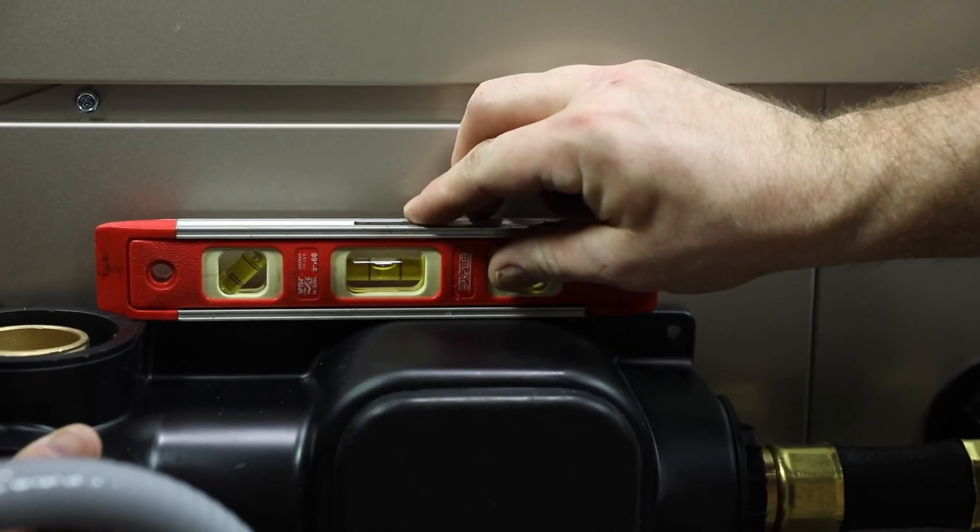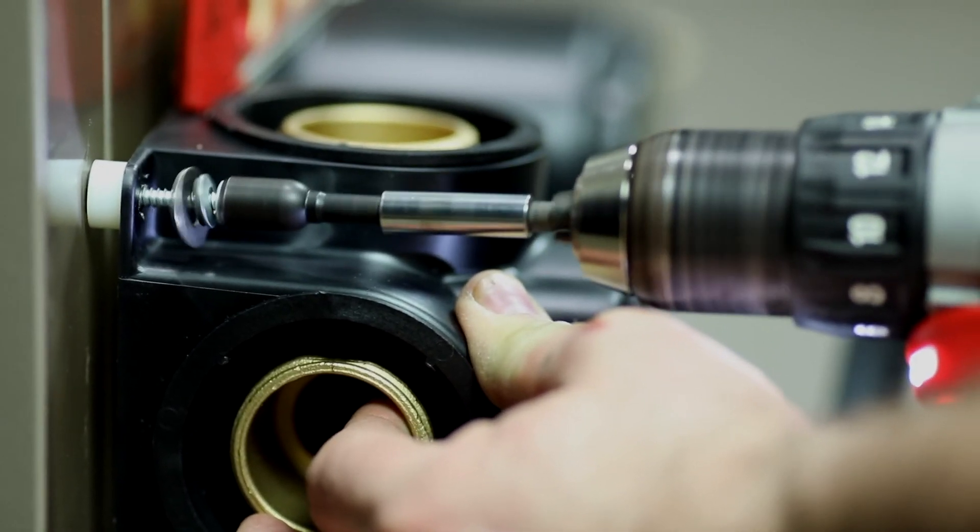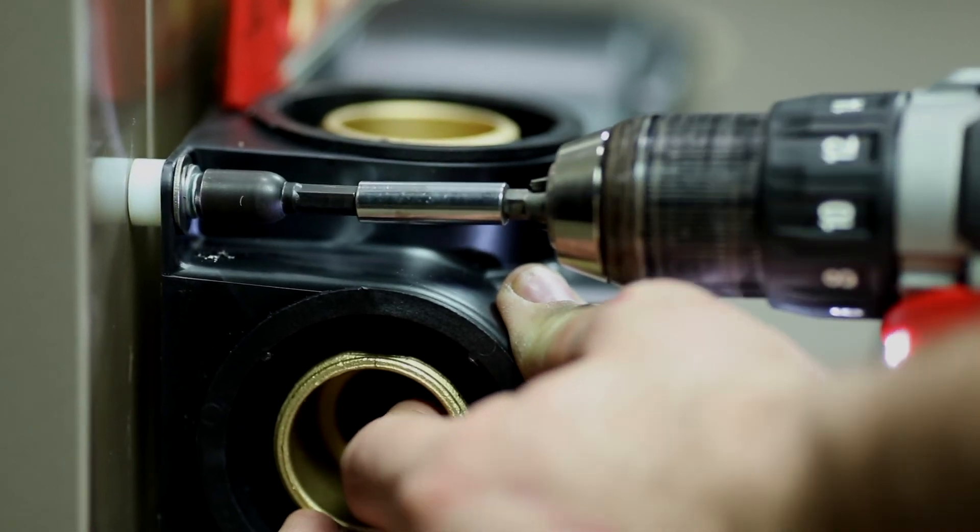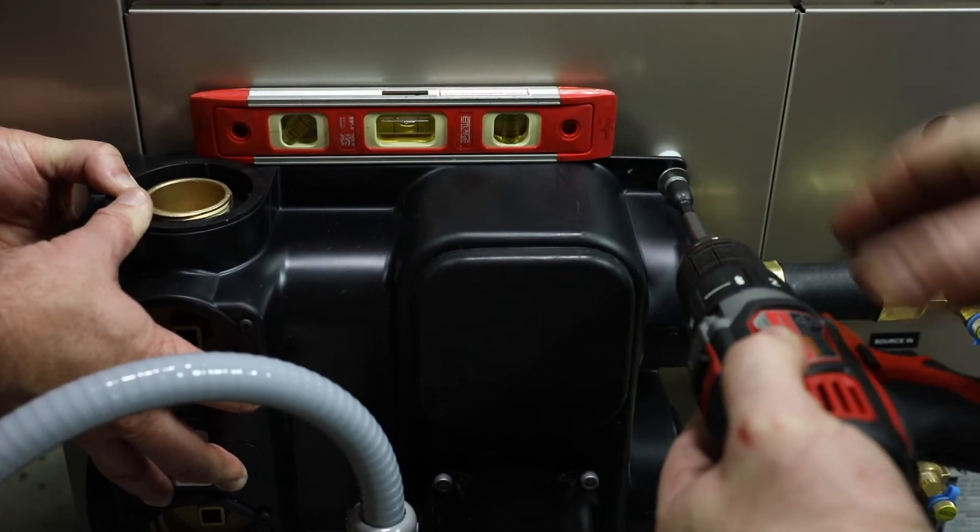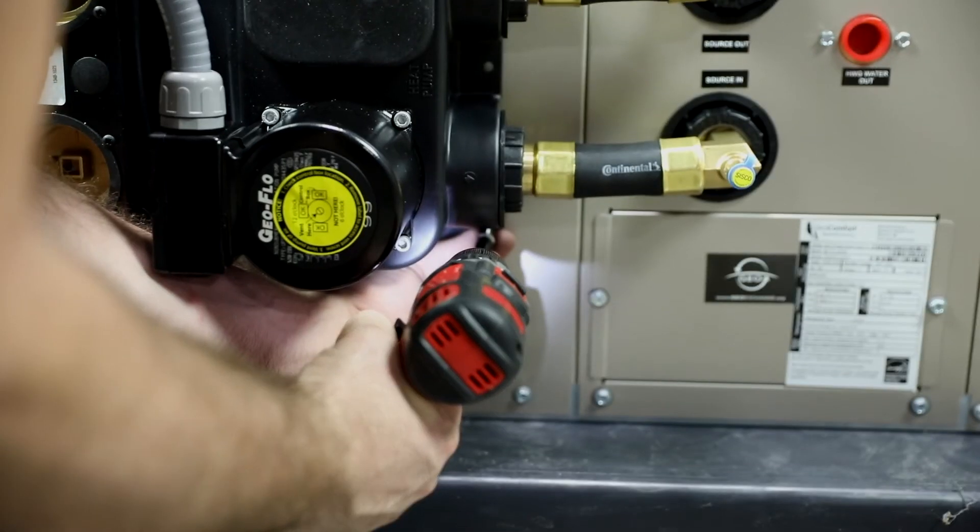It is important to level the flow center. Drive the self-tapping screws into the corner post and then panel one at a time. Do not over tighten to avoid stripping the sheet metal panels. We recommend starting with the top corner post screw and check if it's level before securing the remaining three screws.